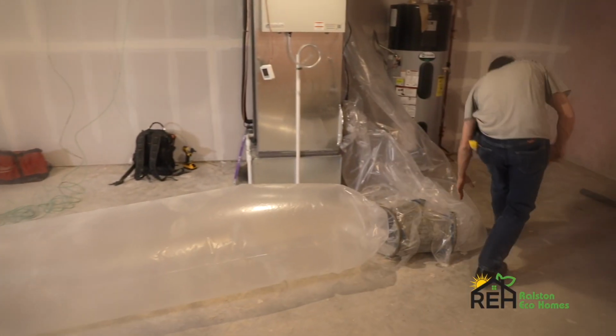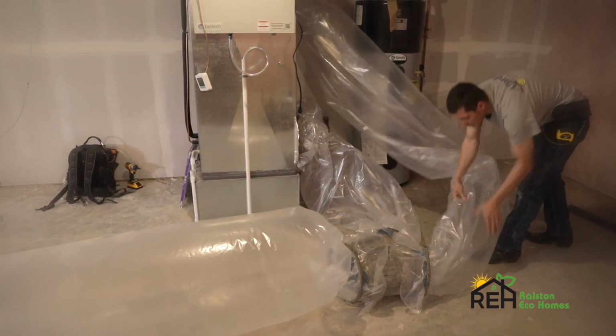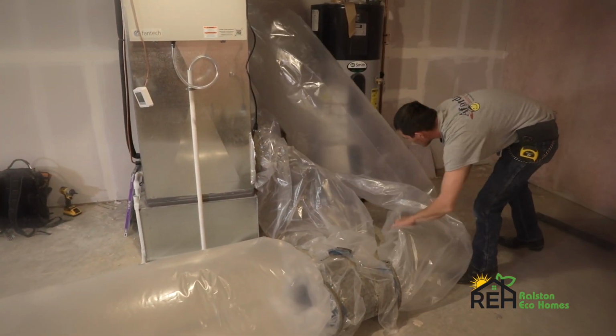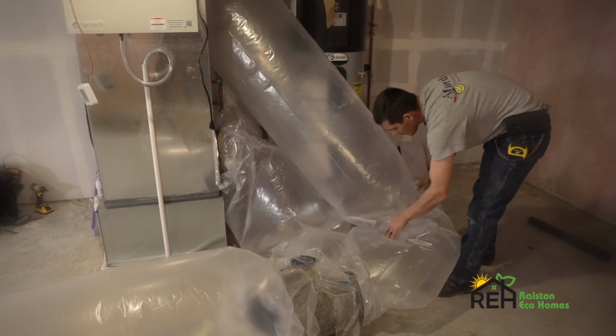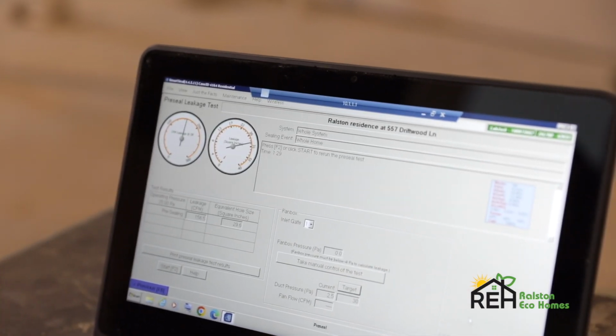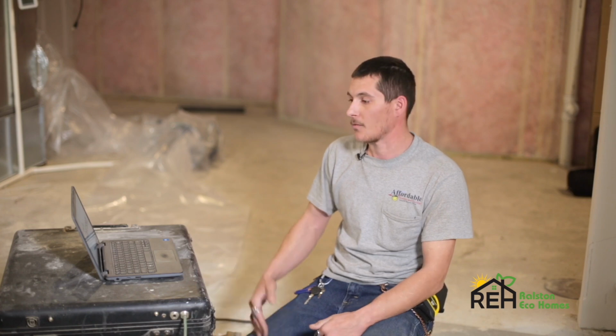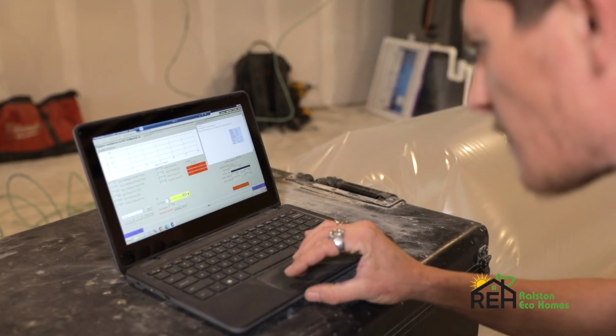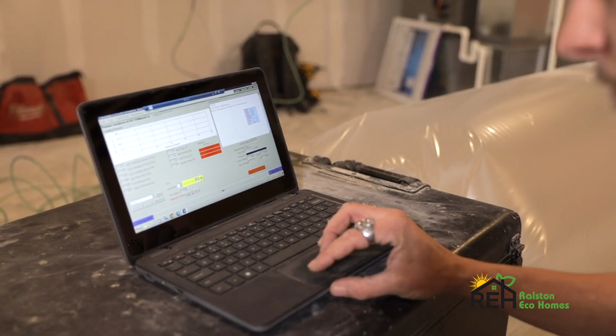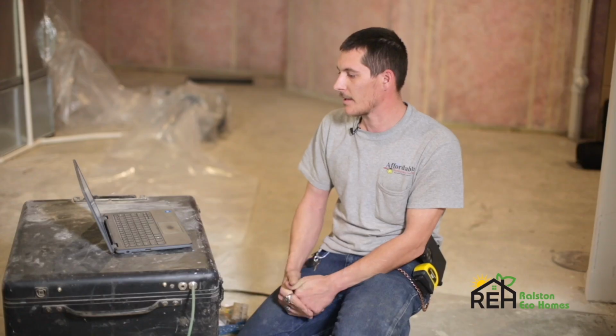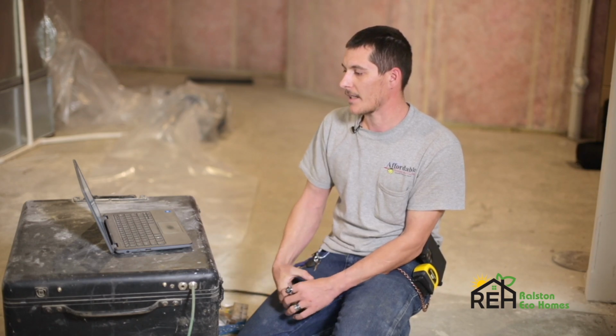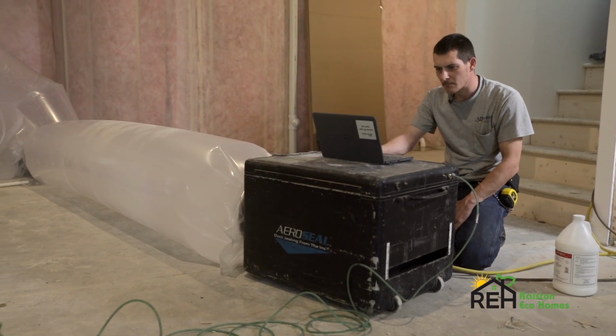So once we open up the program, then we'll do a pre-seal. And the pre-seal is going to tell us how much leakage there is actually right now before we've released any sealant into the system. And then we'll seal it, and then we'll do a post-seal when we're done, so we can see what our number difference is. We can see what we started with and how much we sealed of the system by a percentage, and how much CFM we've saved. Then typically we're trying to get down to 6% of the square footage. That's what the code is, but I try and go to at least 3% of the square footage.